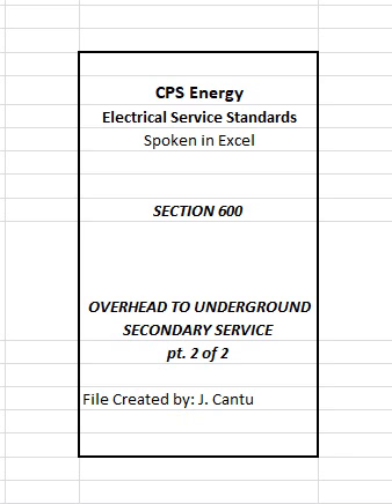1. Sleeves shall consist of a 6-inch Schedule 40 or Schedule 80 PVC conduit installed on spacers every 4 feet and staked down at every 5 to 7 feet. One sleeve is required for each underground service lateral conduit specified by CPS Energy to be installed within trench.